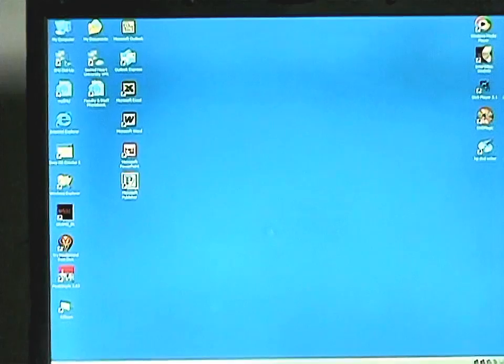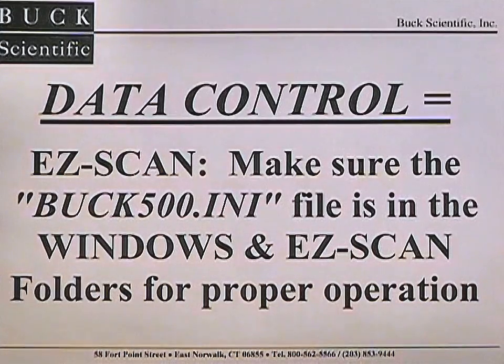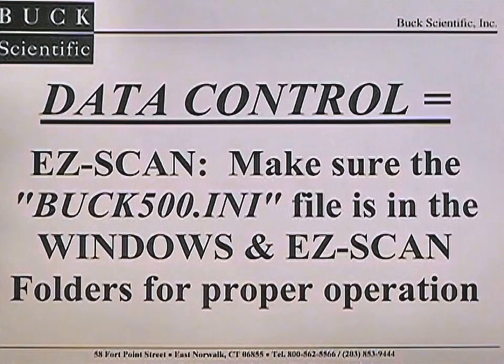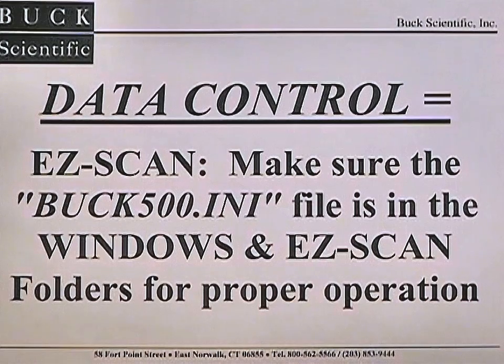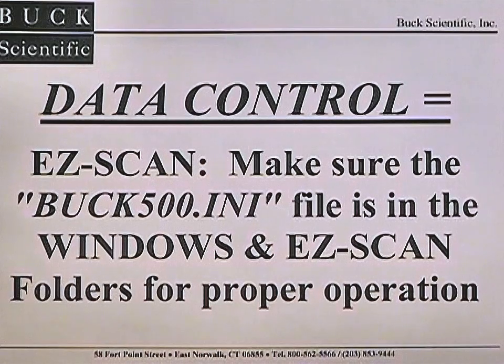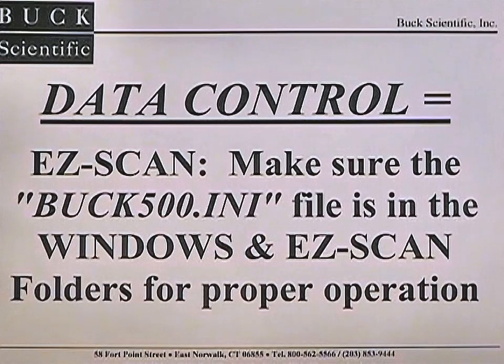Make sure the M500 is turned on, and then we can begin using the Easy Scan software. Buck Scientific cannot be liable for the setup and BIOS configuration of your particular computer, unless it is purchased from Buck Scientific. Please make sure that the Buck 500 INI file is copied to the Windows folder and the Easy Scan folder for proper communication parameters and operation of the system.